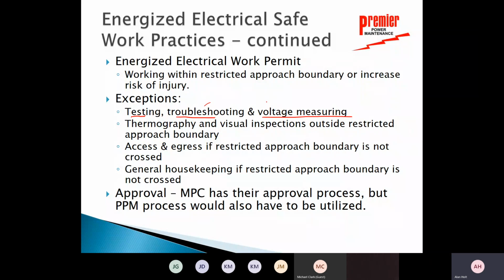Testing, troubleshooting, voltage measuring. If you're going to troubleshoot a piece of equipment, it's got to be energized. We have to do voltage measuring in order to verify that it's de-energized before we can apply grounds. So those parts are important. But the second that we get past testing, troubleshooting, and voltage measurement and get a tool out of our hand to actually perform some task inside that boundary, that requires an energized work permit.